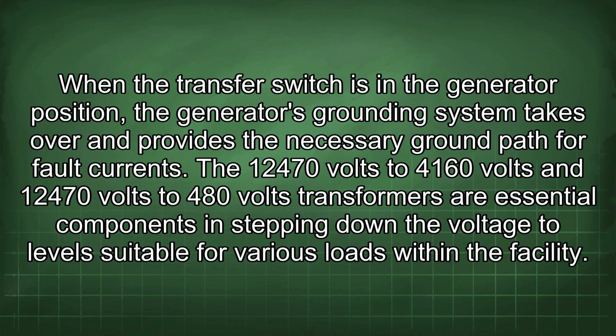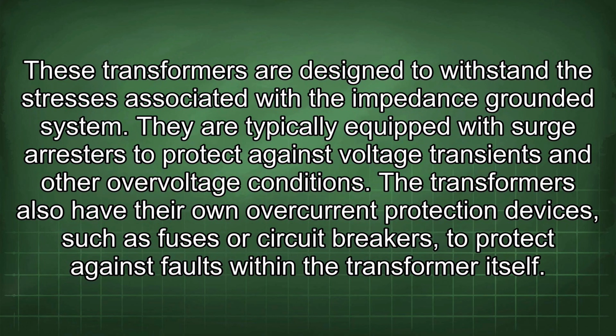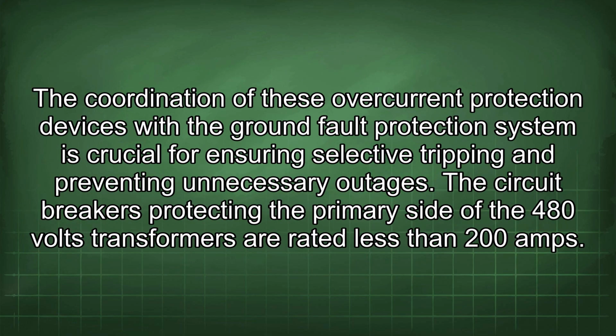The 12,470 volts to 4,160 volts and 12,470 volts to 480 volts transformers are essential components in stepping down the voltage to levels suitable for various loads within the facility. These transformers are designed to withstand the stresses associated with the impedance-grounded system. They are typically equipped with surge arresters to protect against voltage transients and other overvoltage conditions. The transformers also have their own overcurrent protection devices such as fuses or circuit breakers to protect against faults within the transformer itself. The coordination of these overcurrent protection devices with the ground fault protection system is crucial for ensuring selective tripping and preventing unnecessary outages.